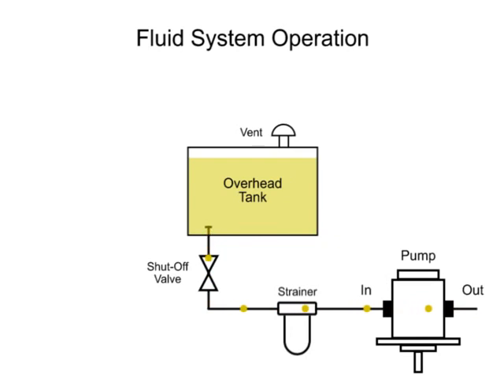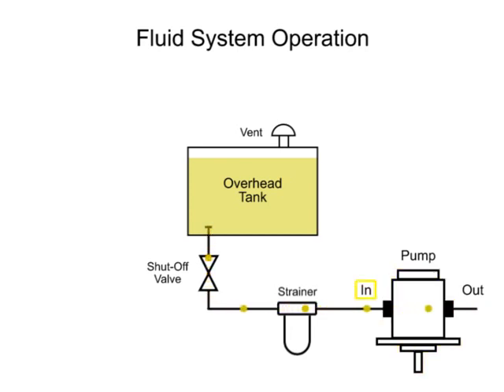The placement of fluid system components in relation to each other is critical to successful operation of the system. Fluid naturally flows from areas of high pressure to areas of low pressure. Pumps operate by creating low pressure at the inlet, which allows liquid to be pushed into the pump by atmospheric or pressure head.